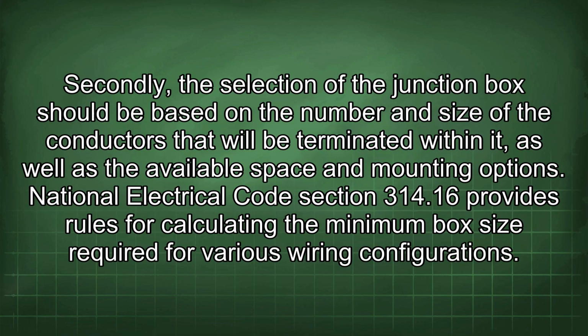Secondly, the selection of the junction box should be based on the number and size of the conductors that will be terminated within it, as well as the available space and mounting options. National Electrical Code Section 314.16 provides rules for calculating the minimum box size required for various wiring configurations.